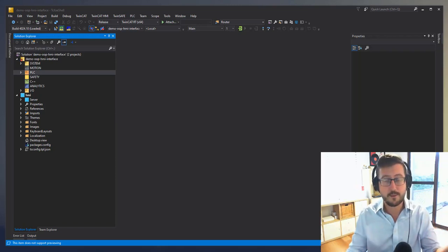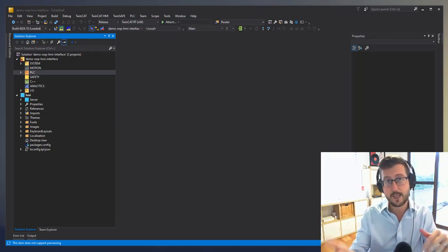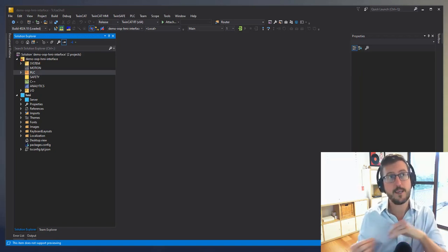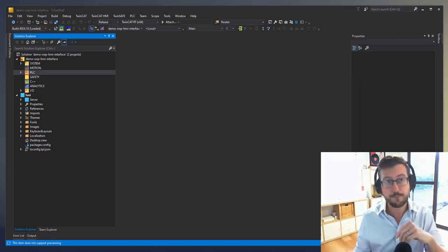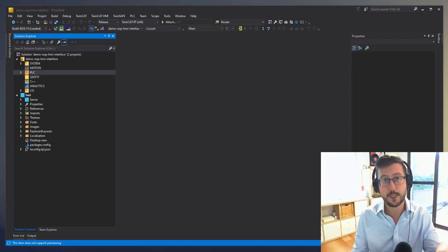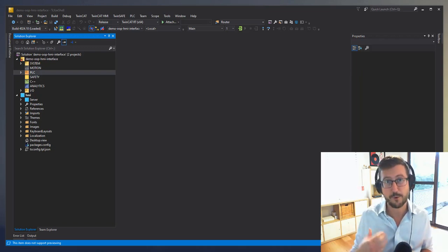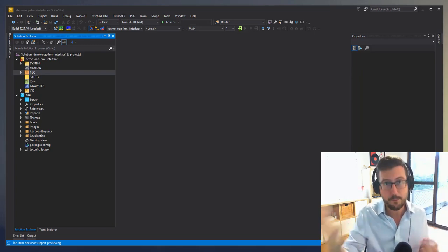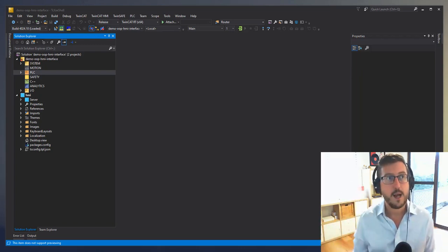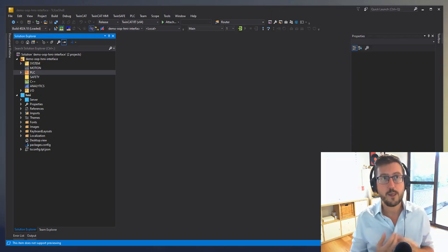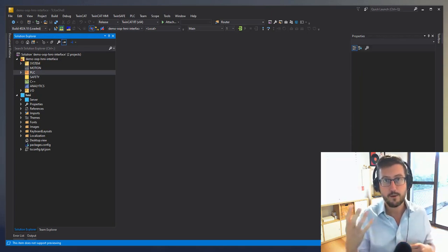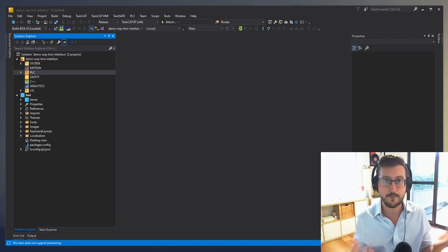Obviously, there's lots of ways of writing programs, not necessarily saying any are better than others. But if you take an object-oriented programming approach, you have objects that require parameters from your HMI. When I say parameters, I tend to talk in terms of things which are read-only for the program, where I tend to speak status as being things which I can write back and tell people, whether it be the HMI or something else. So quite often we will want to decouple our objects from the HMI itself.